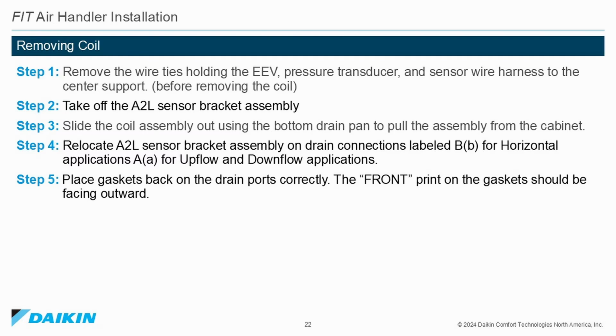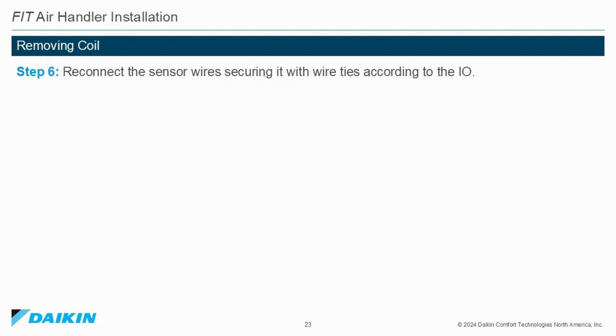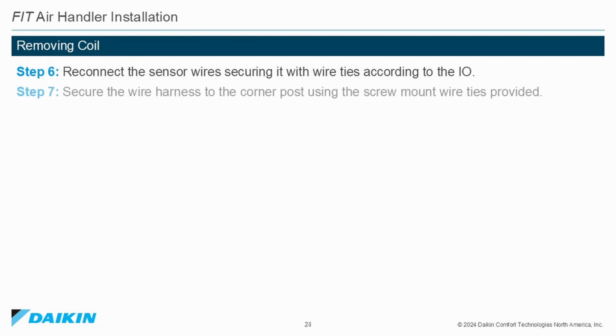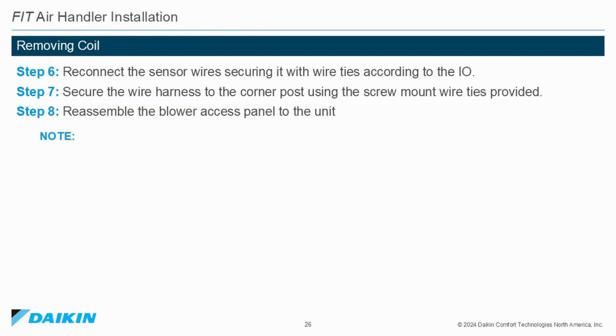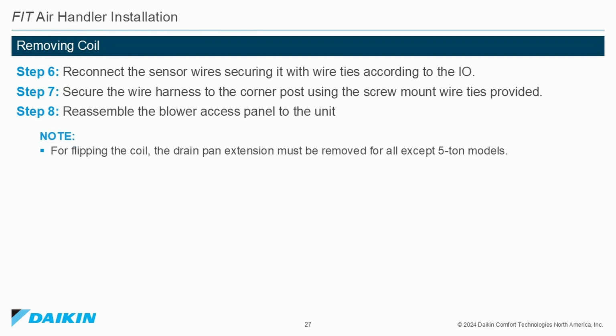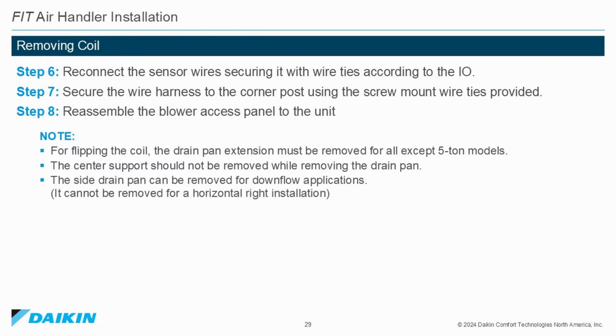The front print on the gasket should be facing forward. Step 6. Reconnect the sensor wires, securing it with wire ties according to the installation and operation manual. Step 7. Secure the wire harness to the corner post using the screw mount wire ties provided. Step 8. Reassemble the blower access panel to the unit. For flipping the coil, the drain pan extension must be removed for all coils except for 5-ton models. The center support should not be removed while removing the drain pan. The side drain pan can be removed for downflow applications. It cannot be removed for horizontal right applications.